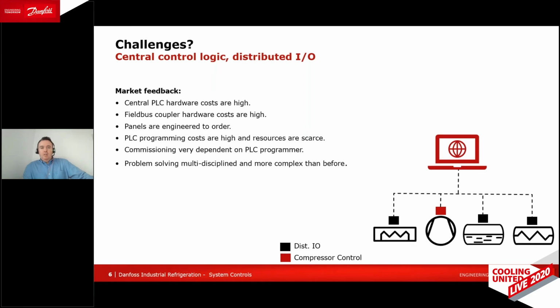In terms of problem solving, for smaller projects within Europe, a lot of the I/O would traditionally be wired directly back to the central PLC. This has become less common over the last 20 years because the cost of wiring and labor has increased, so we've got a lot more distributed I/O panels. The problem solving, where you're changing from an analog signal to a bus signal and then wiring that back to the PLC with a field bus connection, becomes a little bit more complex.